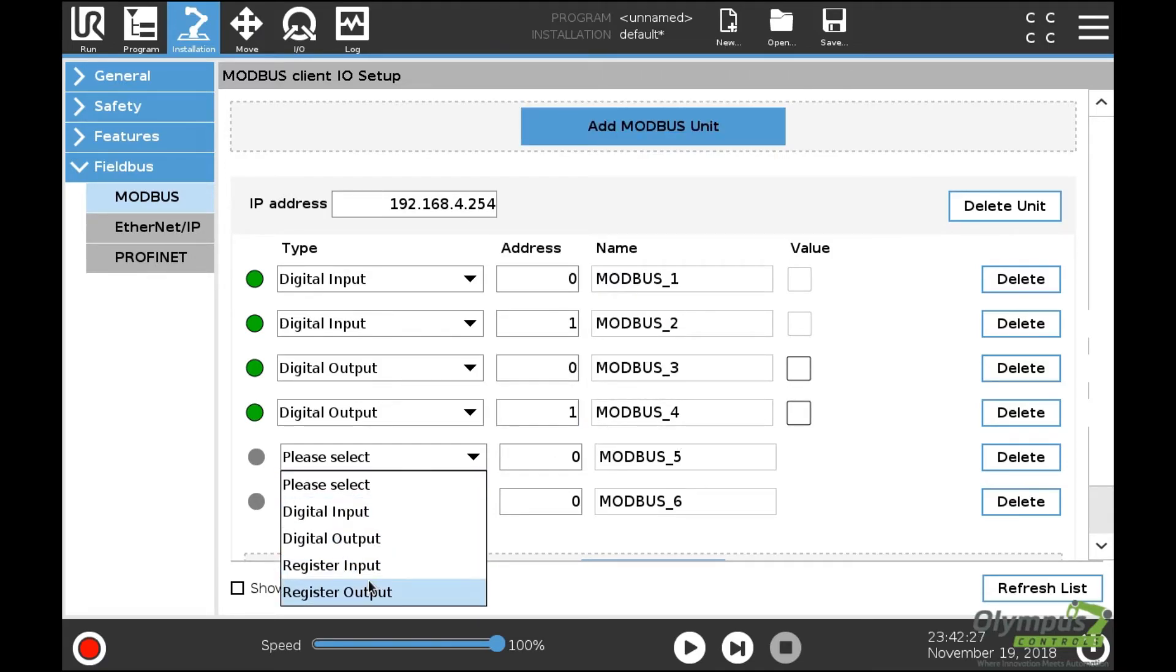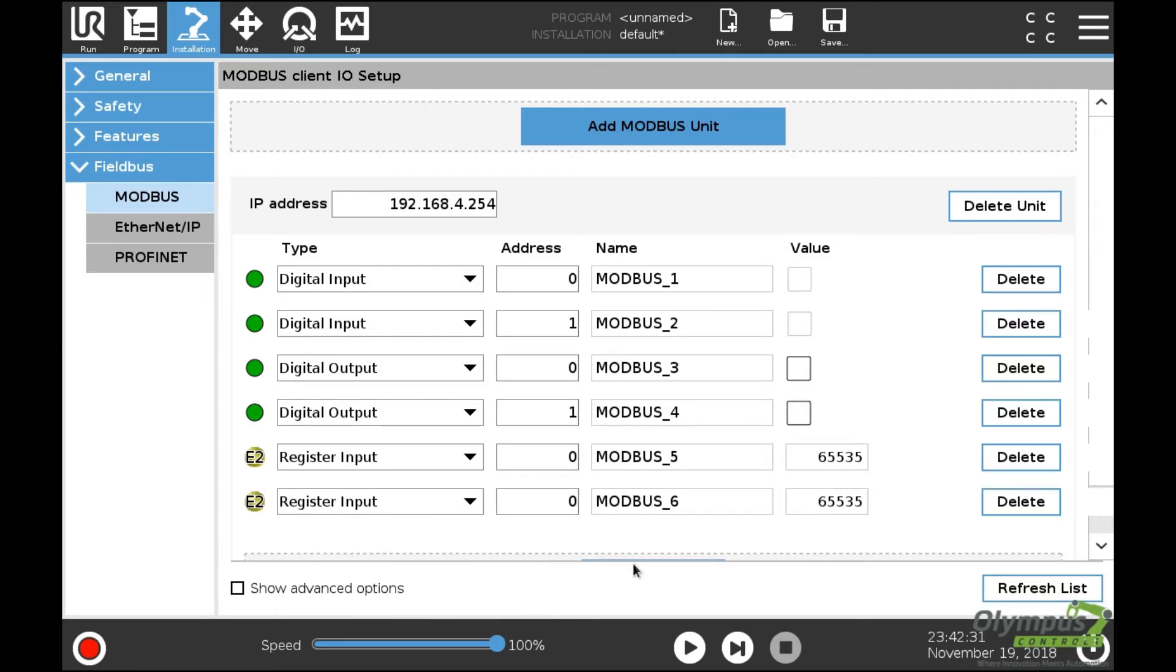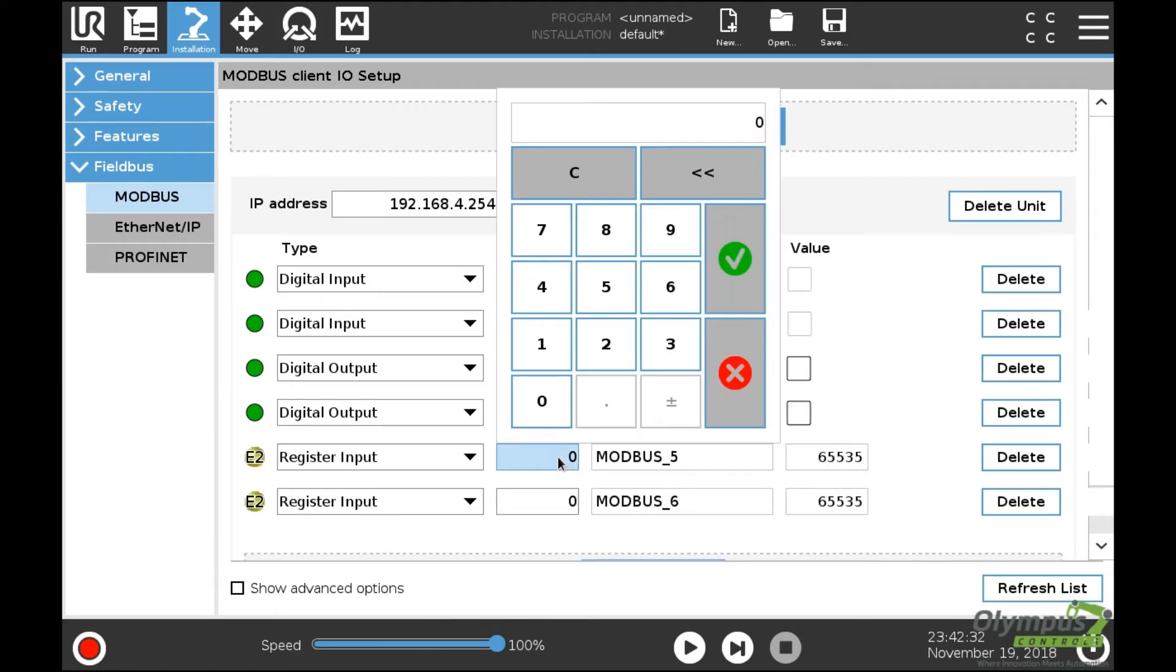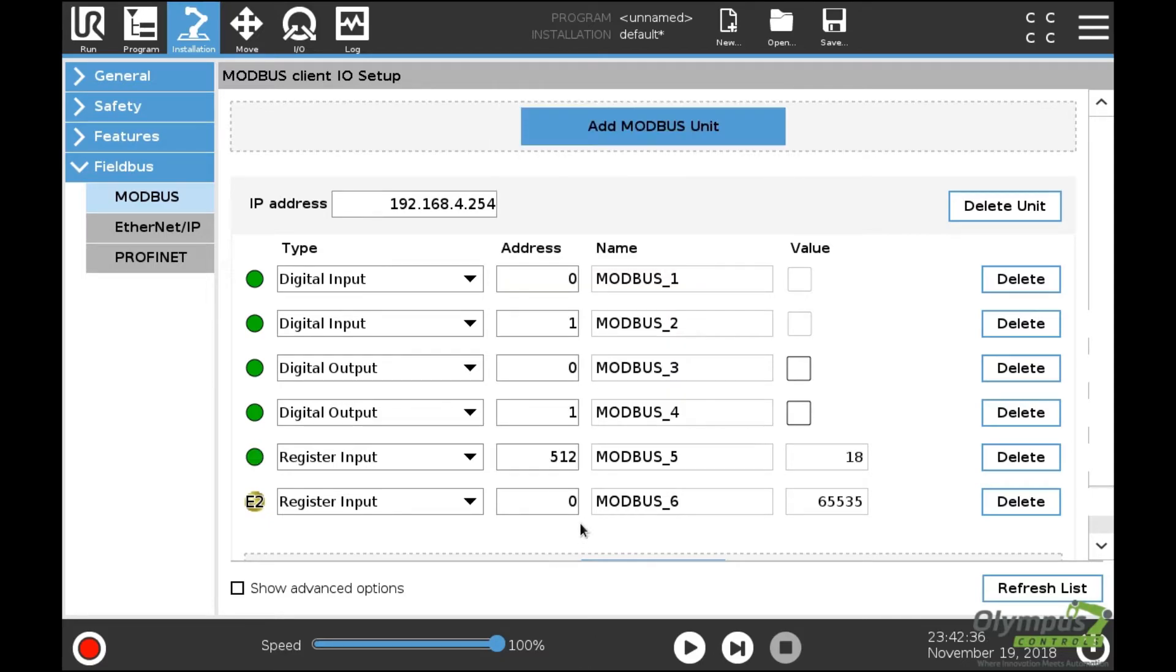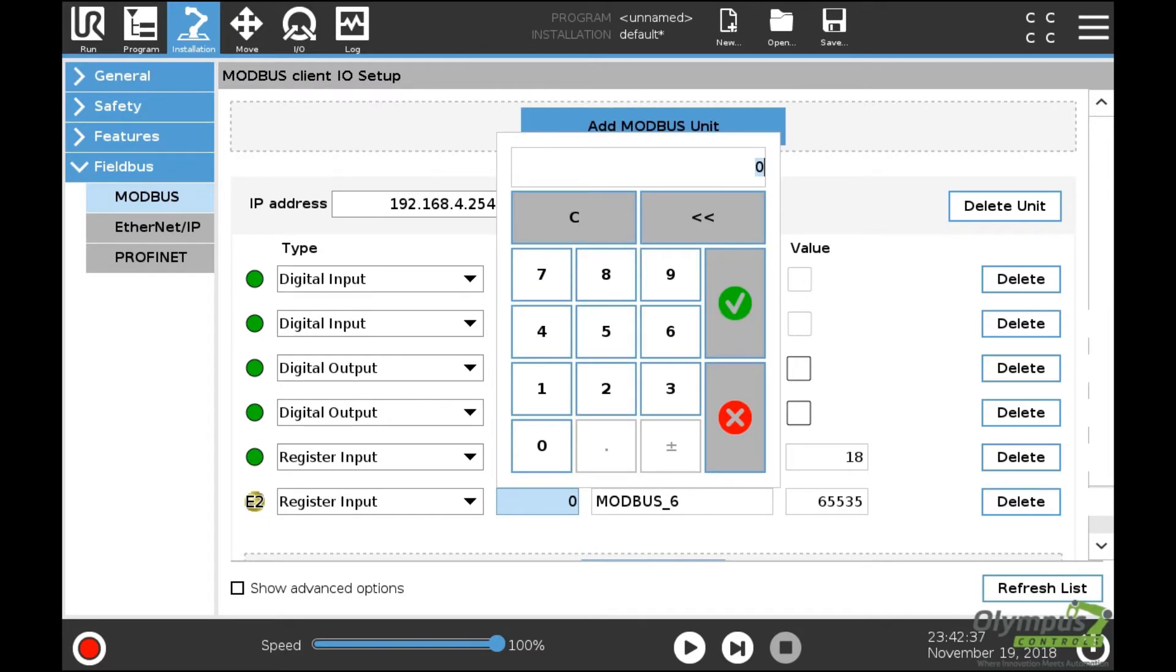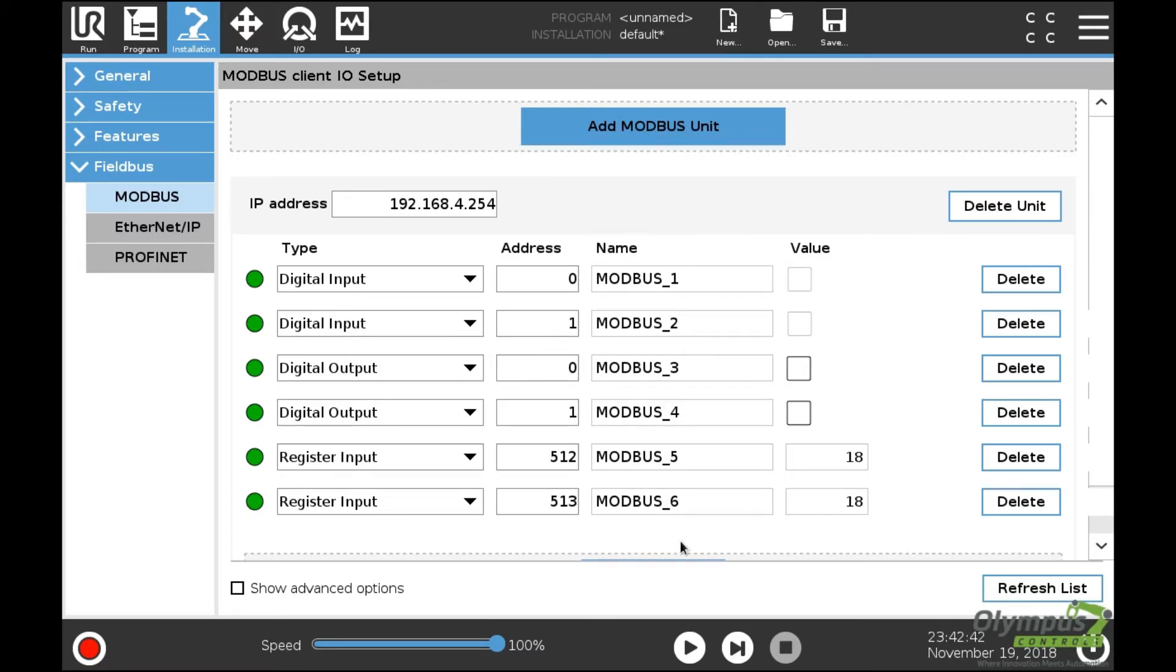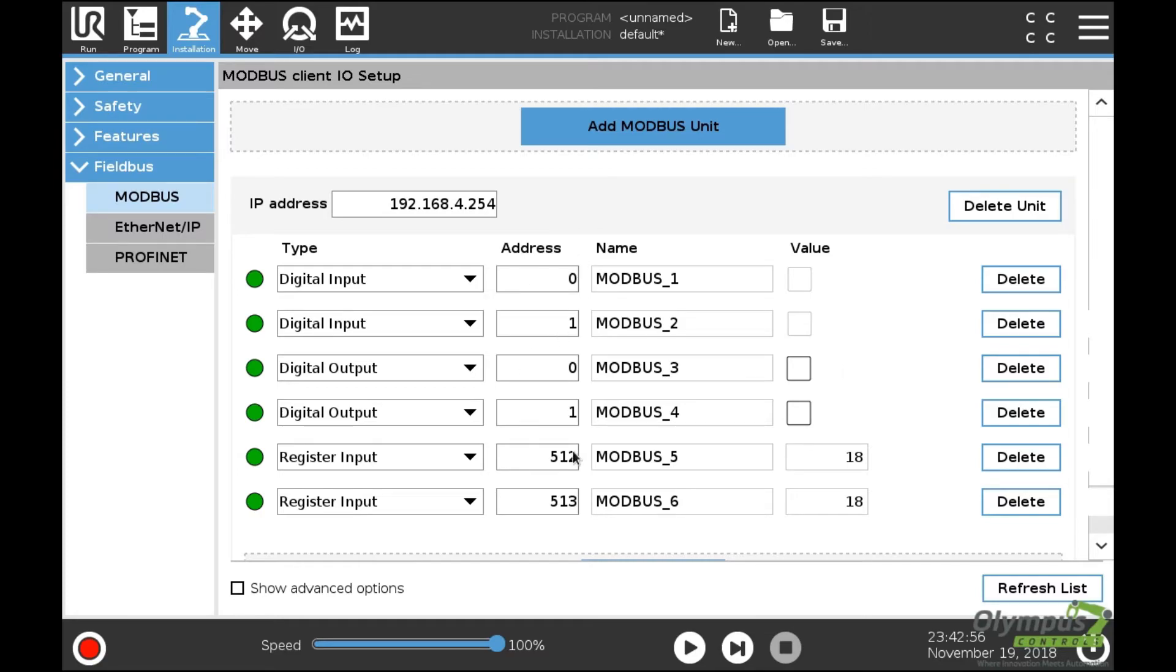Our analog inputs are actually register inputs. The register input starts at address 512 for analog input zero and 513 for analog input one. The default address mapping can be found in the Moxa ioLogik user manual, which is well documented. If you have questions about Modbus addressing or want to change addresses, you can find that information in the Moxa ioLogik manual.